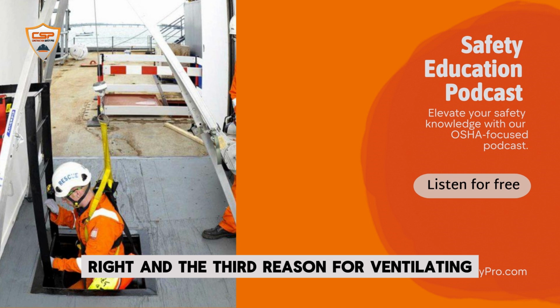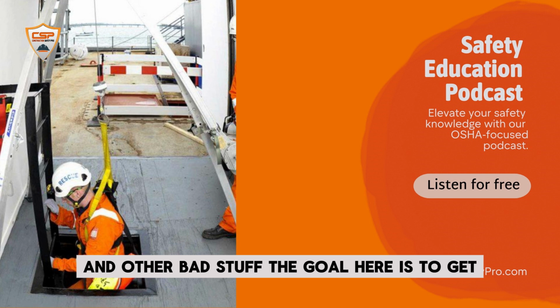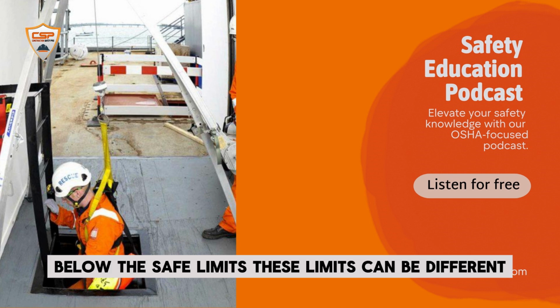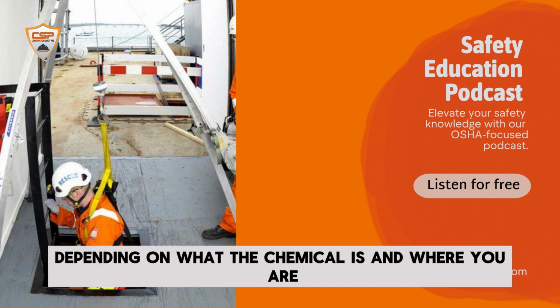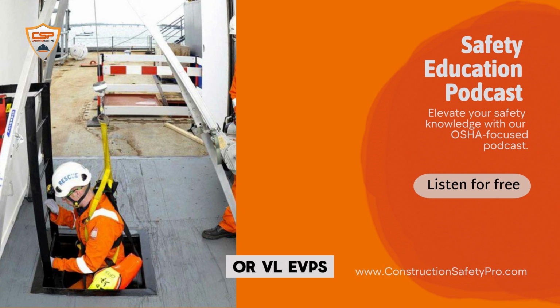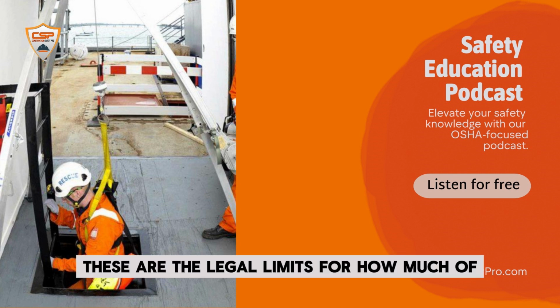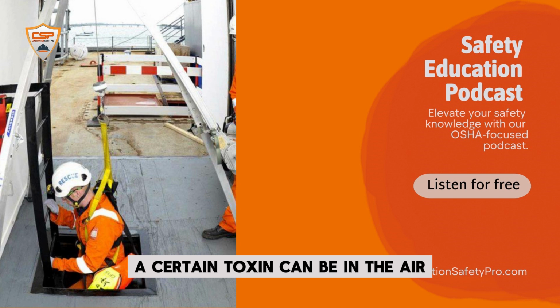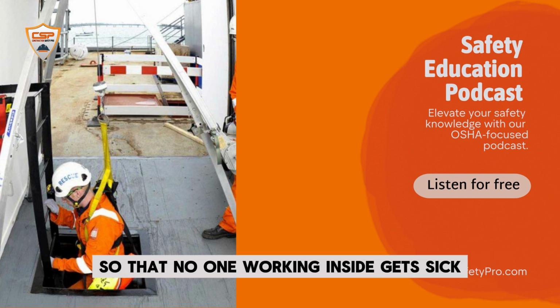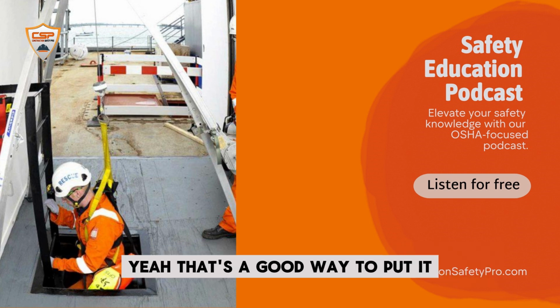Right. And the third reason for ventilating is to get rid of toxic gases and other bad stuff. The goal here is to get the concentration of those substances down below the safe limits. These limits can be different depending on what the chemical is and where you are. You might hear people talk about PELs, permissible exposure limits, or VLEPs, which is basically the same thing in French. These are the legal limits for how much of a certain toxin can be in the air. The important thing is to get those levels down so that no one working inside gets sick. So ventilation is kind of like scrubbing the air clean so it's safe for people to be in there and do their jobs. Yeah, that's a good way to put it.